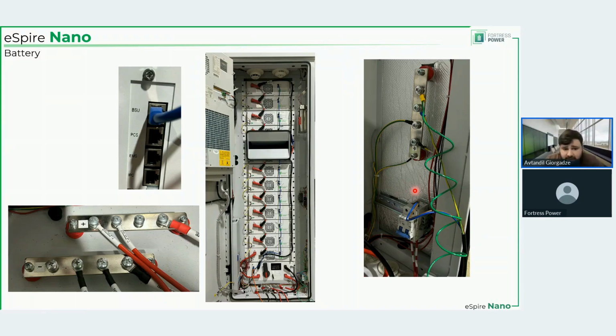So one of the easier ways I can think of doing it would be to use Polaris style connectors and having the cable exiting the backup ports and going to wherever it needs to go, L1, L2, and L3, right? And one of them having Polaris, and that Polaris having connection to this breaker. And then you would also have neutral, or you can take a phase. This has quite a broad range. And then this AC feeds the internal transformers to transform that AC into 24-volt DC that operates the internal circuits. So that's really all there is to the battery.